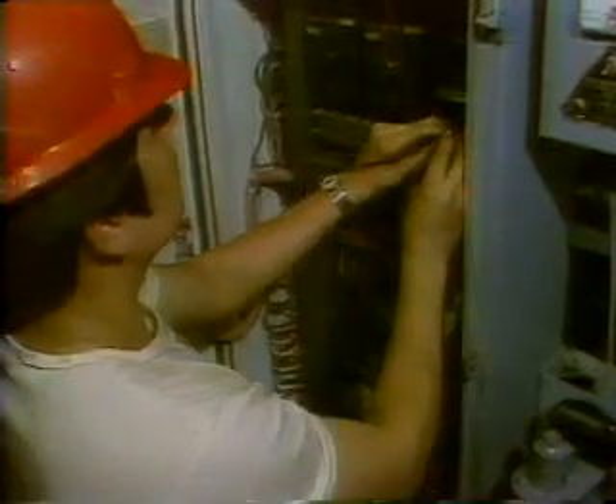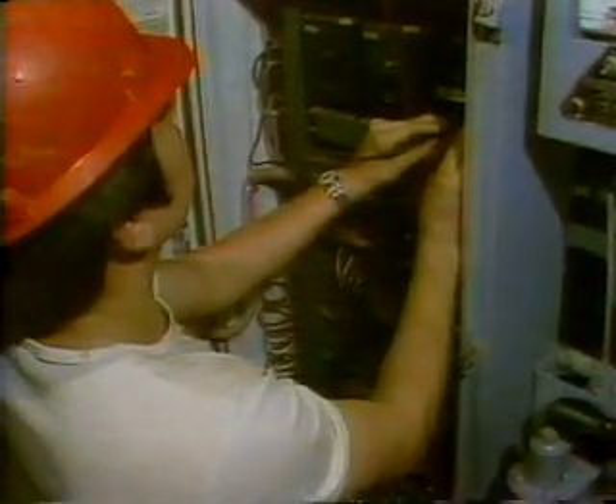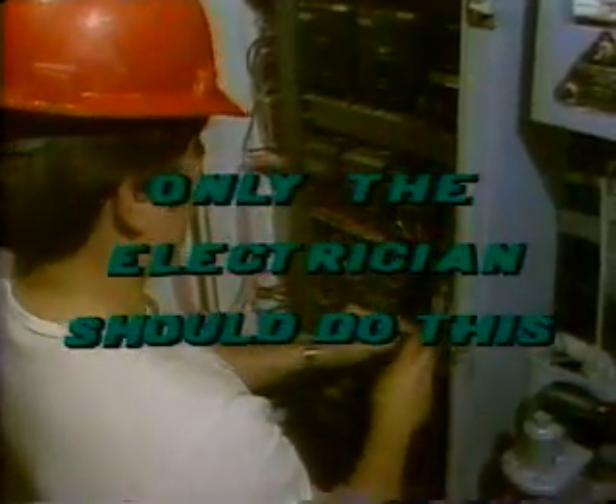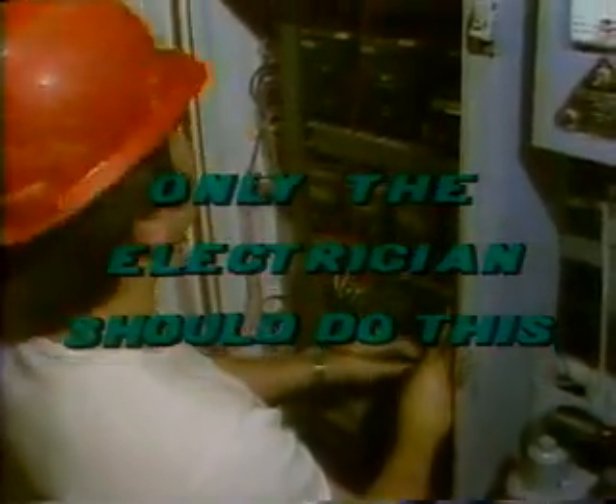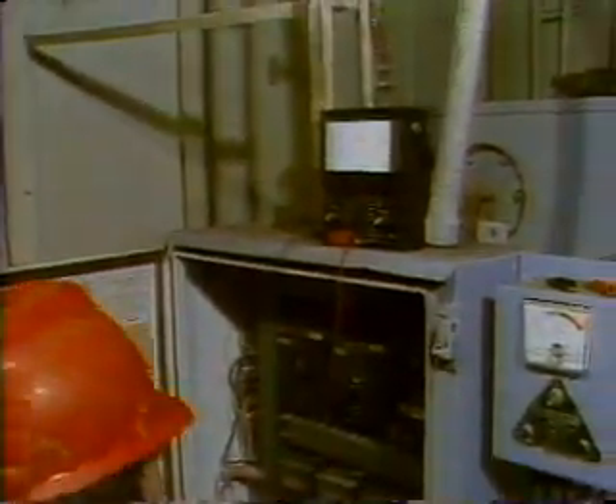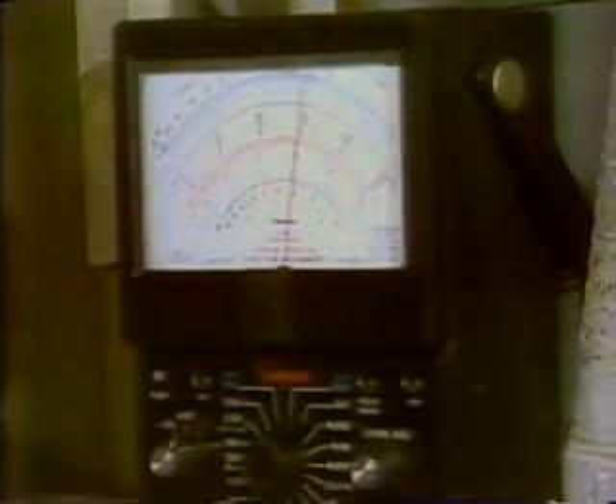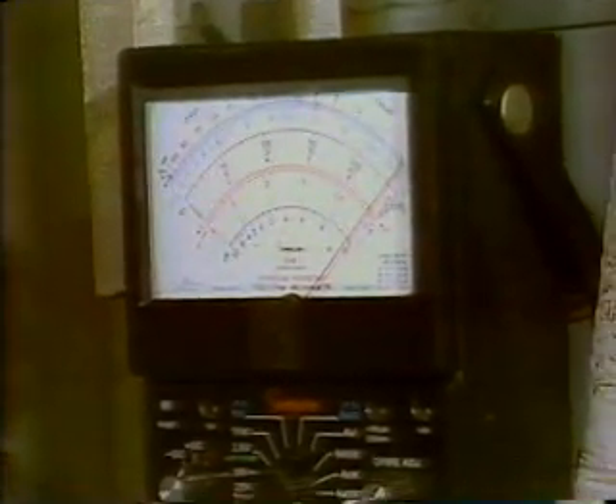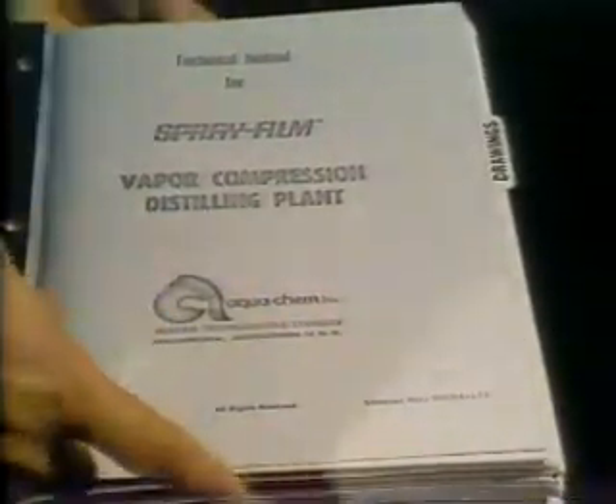These gauges are optional meters and aren't usually included on Sedco's Aquachems, so it'll be necessary to get the rig electrician to take these measurements. Only the rig electrician should take them. Voltage can be taken with a simple volt-ohm meter at the three-phase inlet at the panel main disconnect breaker. The Aquachem manual has the proper specifications for your particular unit.